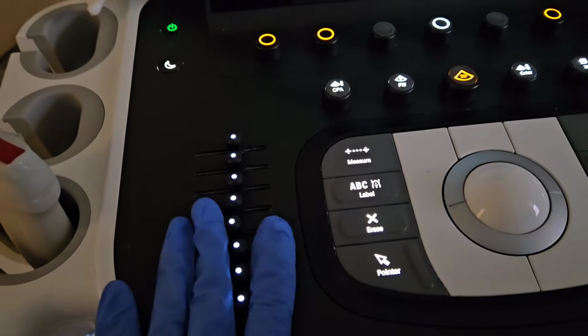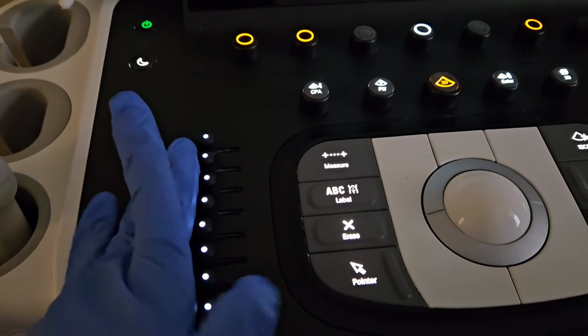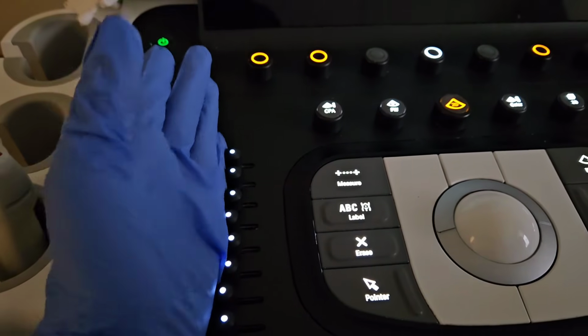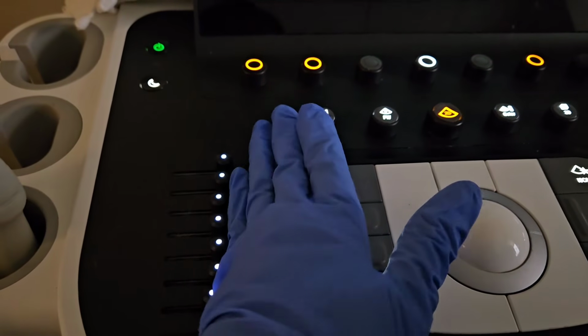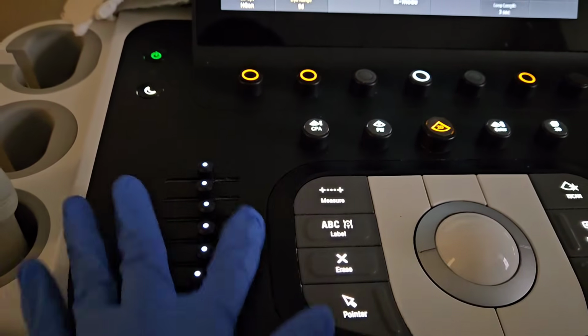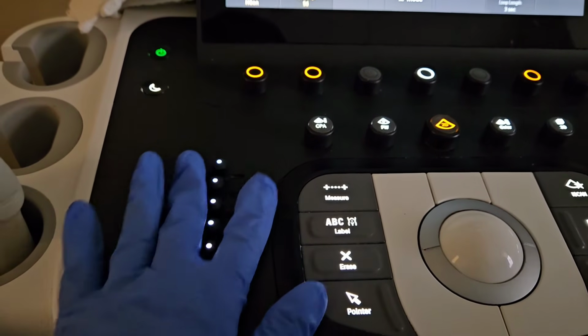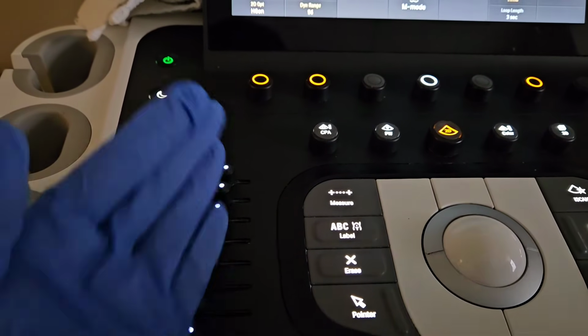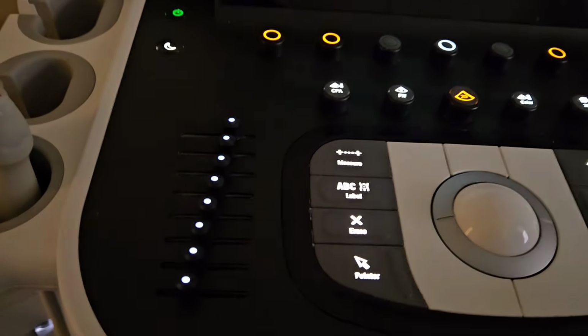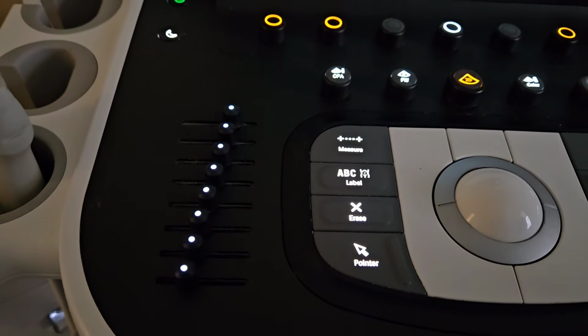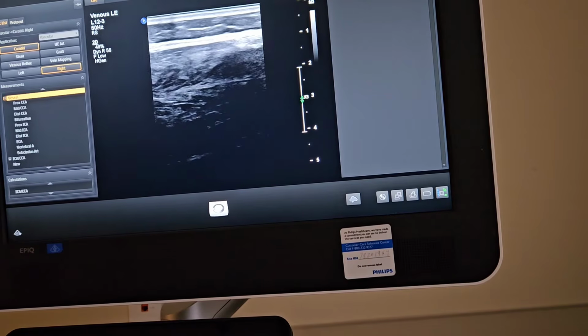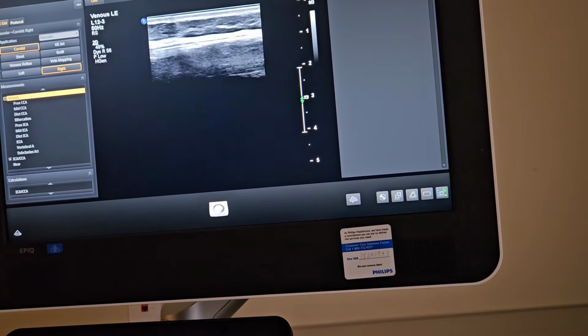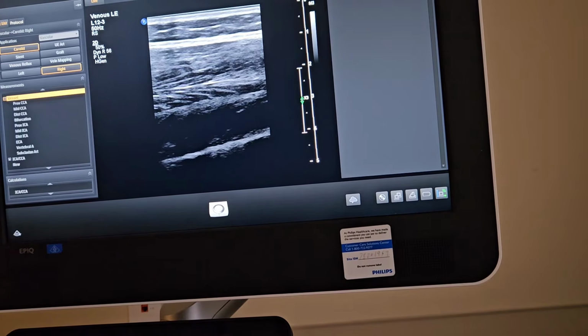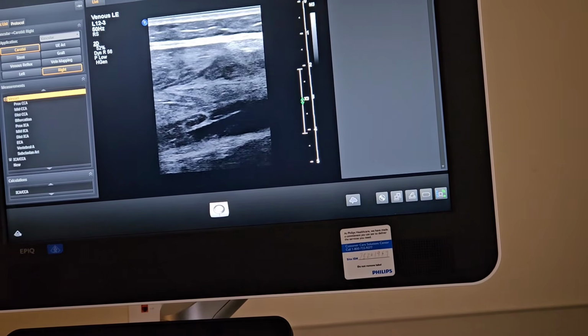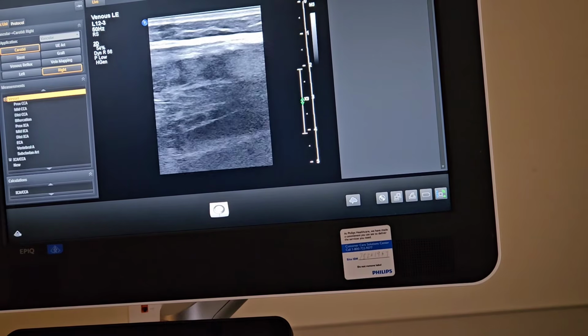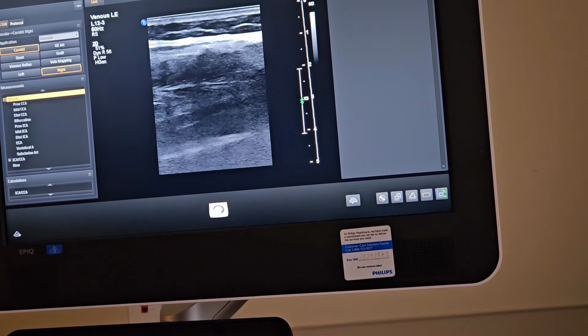Another feature that can help lighten or darken the image is your TGC curve. If you push it over to the right, the lighter your image will be, and over to the left, the darker your image will be. All of these knobs do not have to be at the same level. They can be at an angle, especially if you're compensating for a lot of attenuation that you can see in deeper structures like the liver. Here you see the bottom of this curve is more towards the left, so it's a lot darker on the bottom half of the image. However, when I move those knobs over to the right, you see the bottom of the image gets lighter. You can adjust it so that it's even from top to bottom.